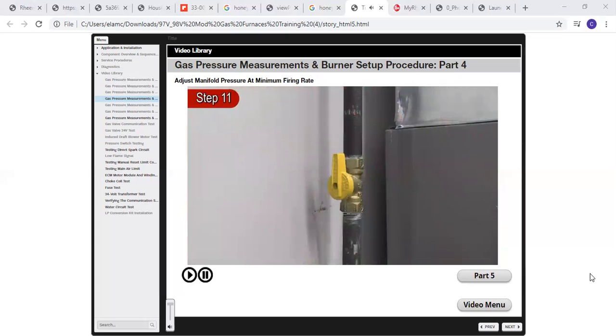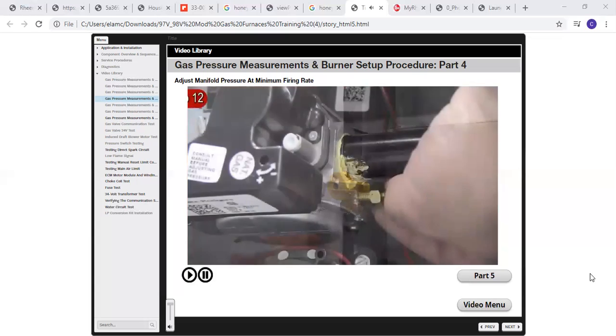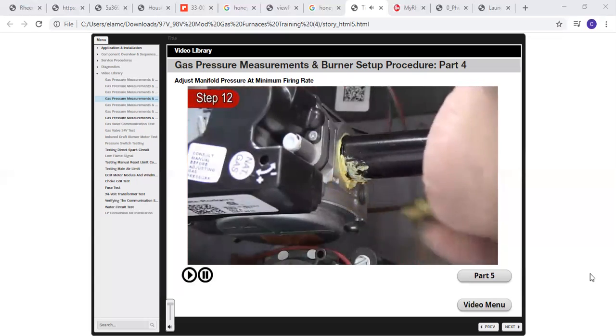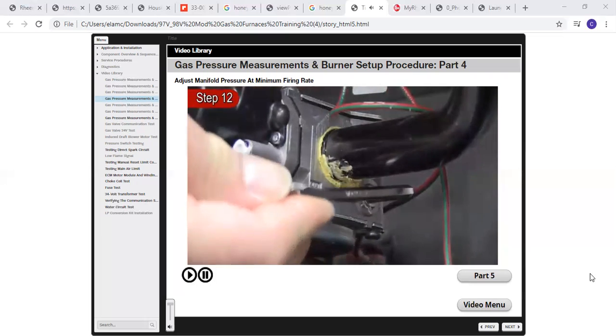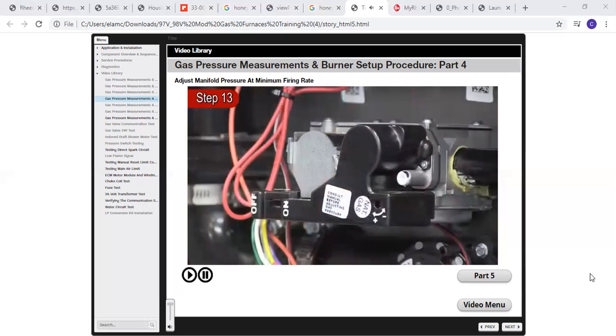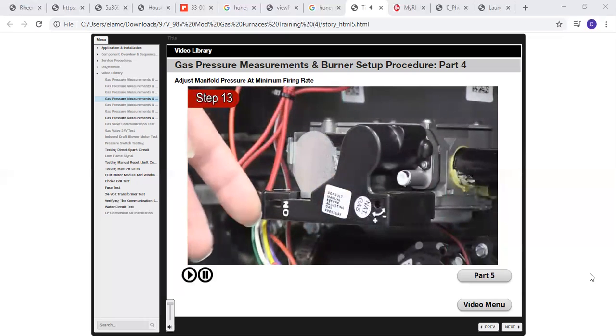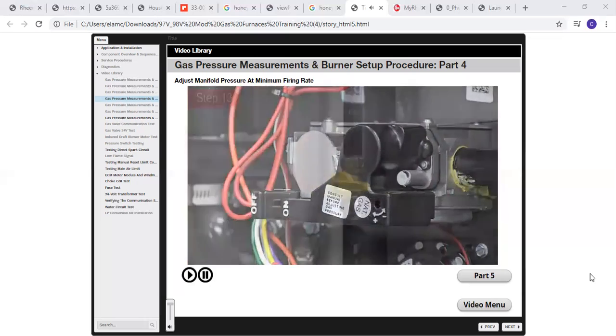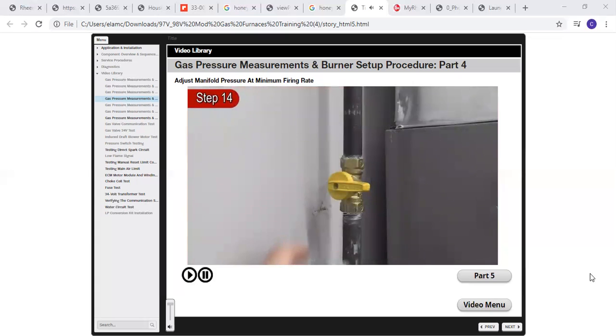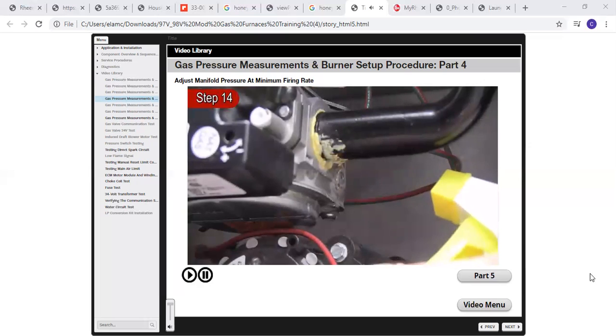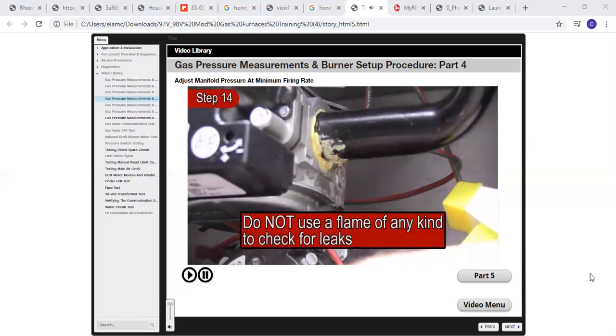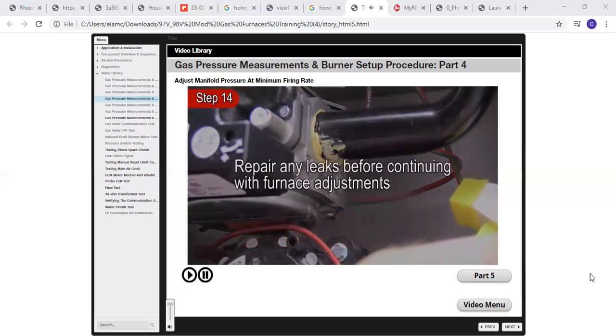Step 11. Turn gas manual shutoff valve located outside the furnace to the closed position. Step 12. Remove manifold pressure cap. Replace and tighten manifold cap plug. Step 13. Slide gas valve on-off switch to the on position. Step 14. Turn gas manual shutoff valve to the open position. Check for gas leaks using an approved leak detector. Do not use a flame of any kind to check for leaks. Repair any leaks before continuing with furnace adjustments.